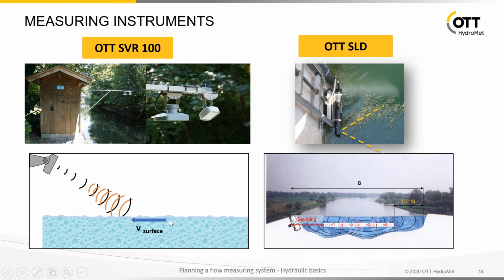A very huge assumption you need to make is that you need to have a rough water surface, otherwise velocity radars will not work. And what you get back is the reflections with a Doppler shift, and from this you can compute the surface velocity. For side-looking Doppler, it's different. You have two acoustic transducers looking sideways into the water and transmitting sound in the direction of flow and against the direction of flow, receiving the reflections from moving particles in the water. And from this you can compute the velocity, as the reflections also come back with a Doppler shift.